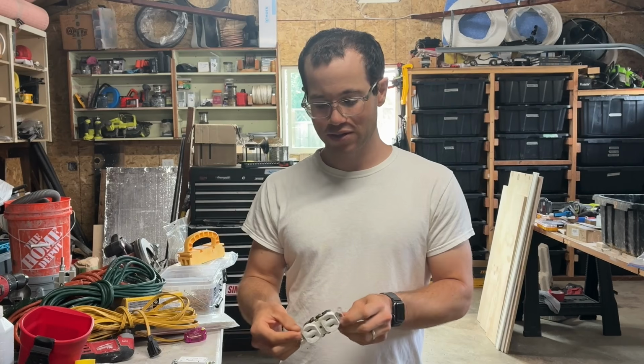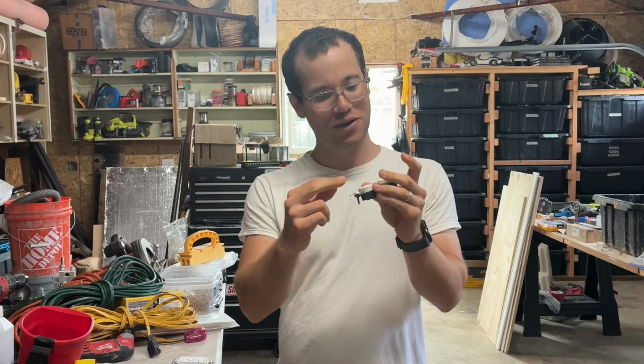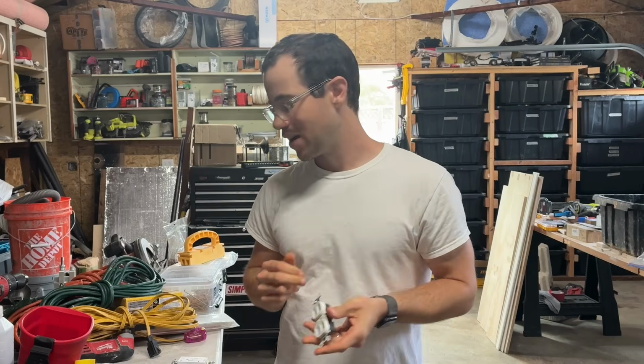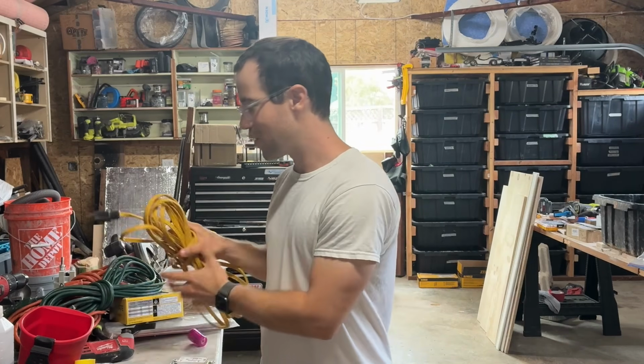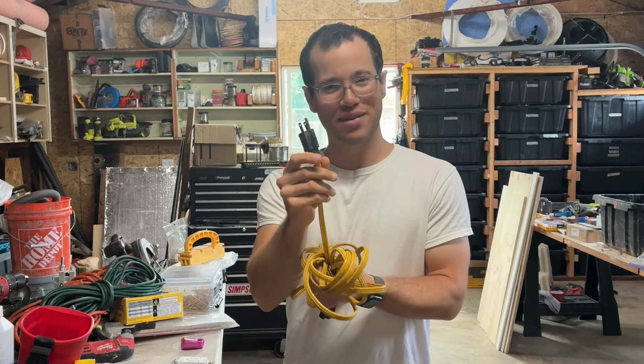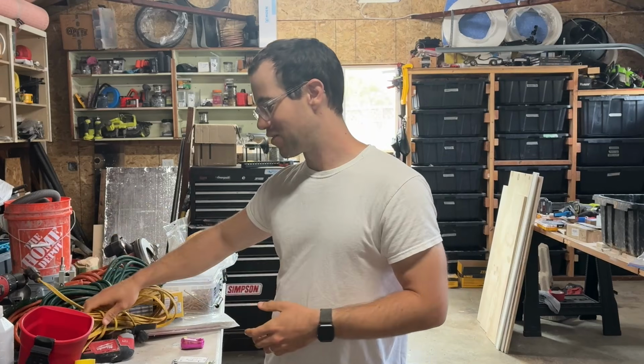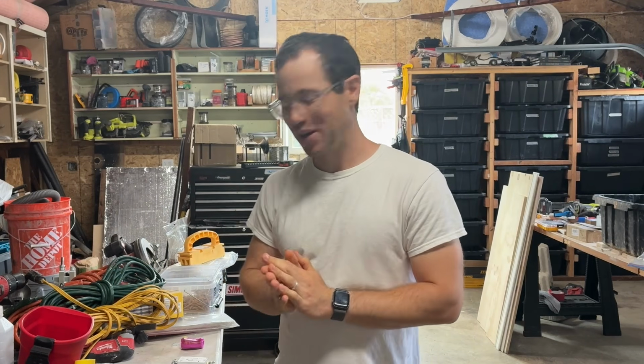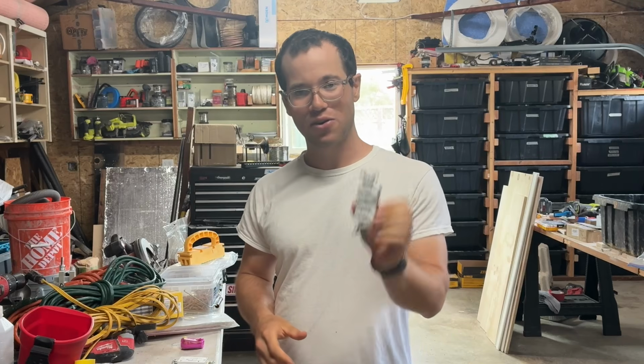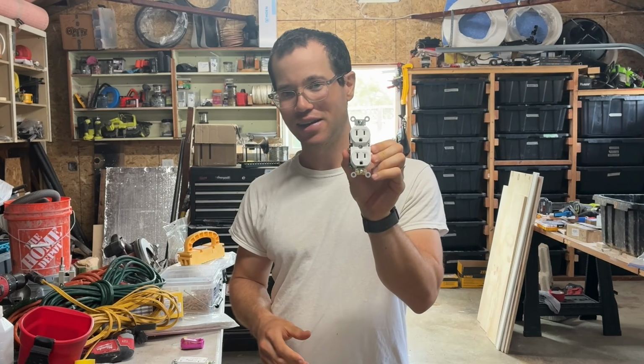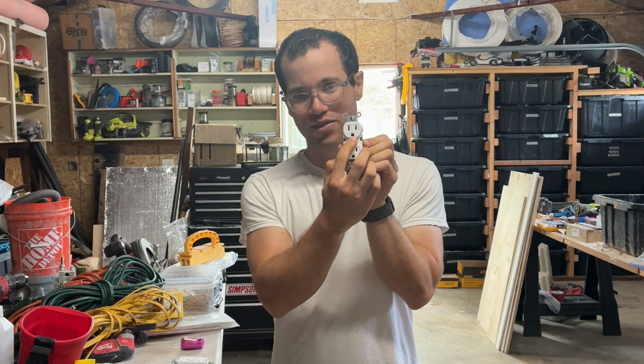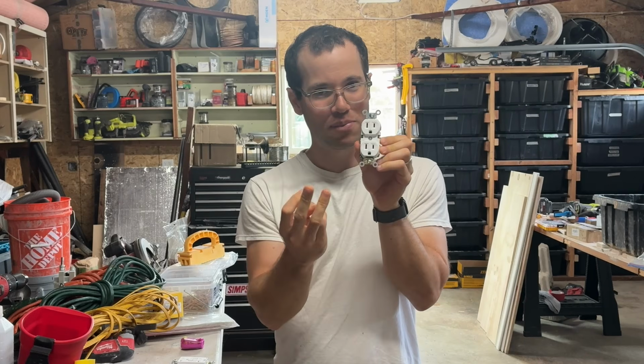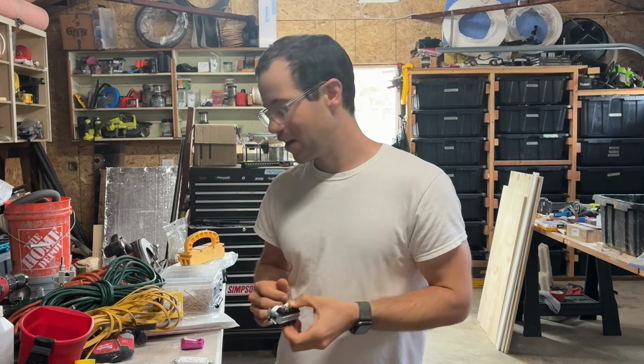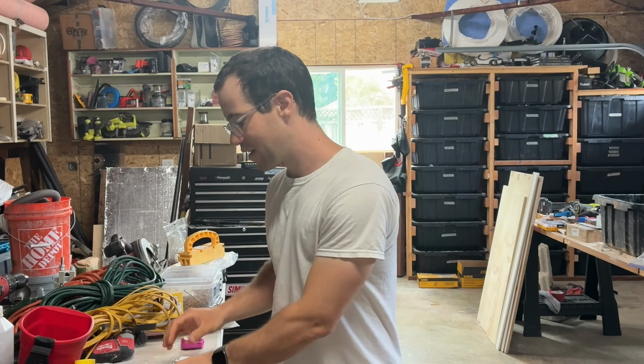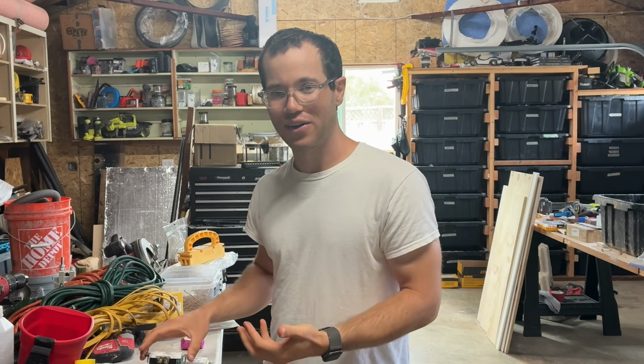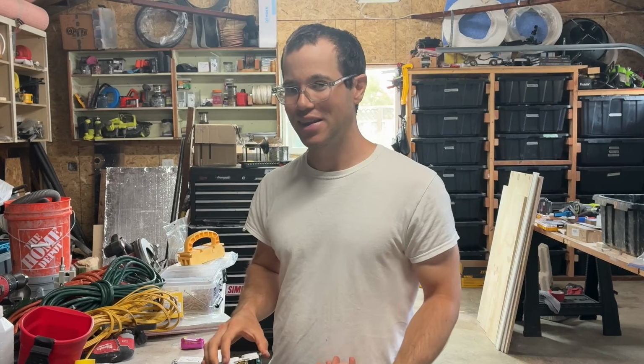So the outlets look like this, with only two prongs. The issue is when you want to plug in something with three prongs, you can't. The not-code-compliant way to fix this is to simply throw in a modern outlet like this, which has that third hole for the three-prong plug. That third prong is your ground, but because you only have two wires, you're not actually grounding anything.